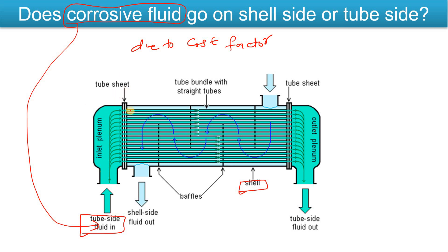The reason is very simple — it is because of the cost factor. The individual tube thickness or individual tube cost will be much cheaper than the entire shell side. The shell side thickness is more than the individual tube. So if the corrosive fluid goes in the tube side, only the tube bundle will be costlier. But if it goes in the shell side, the entire shell will need to be costlier, since shell thickness is higher than the individual tubes.